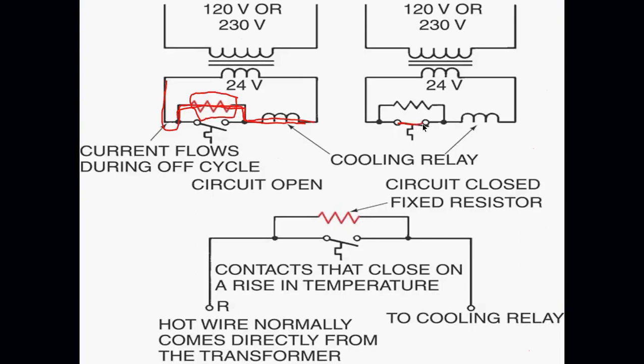Now, when the thermostat closes, this cooling anticipator is no longer the path of least resistance. It comes out of the circuit. It's still connected, but all the current is going to flow through the switch because it has a much lower resistance, and then it's going to get to the coil. Most of these coils are around 14 to 18 ohms, very low resistance. So anytime I have an anticipator, its resistance is always over the resistance of my outdoor coil. So the voltage drop is going to be greater on the resistor than the outdoor coil. The outdoor coil will never get enough voltage to actually operate.